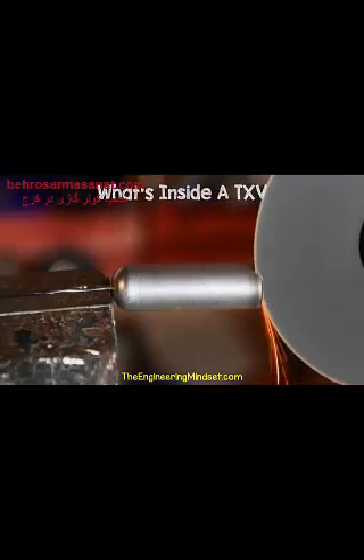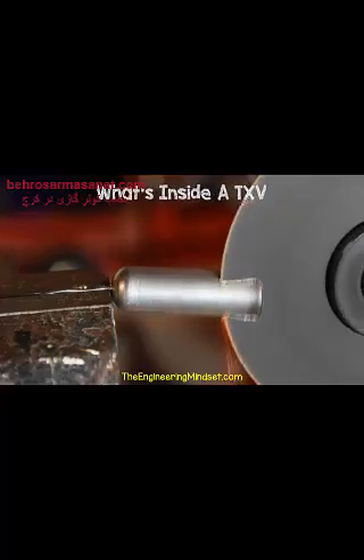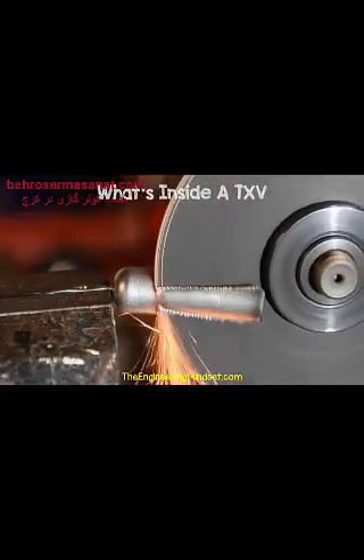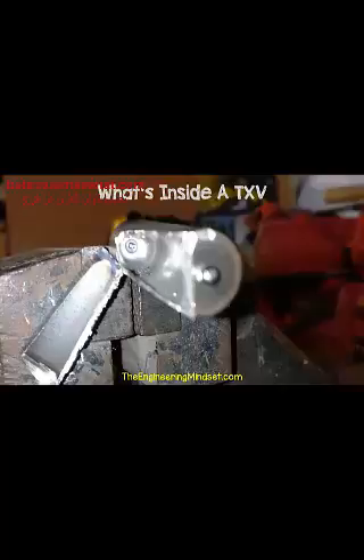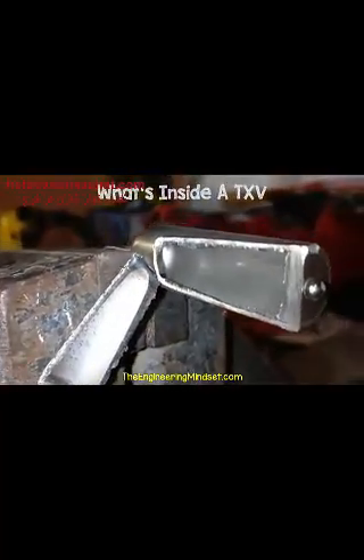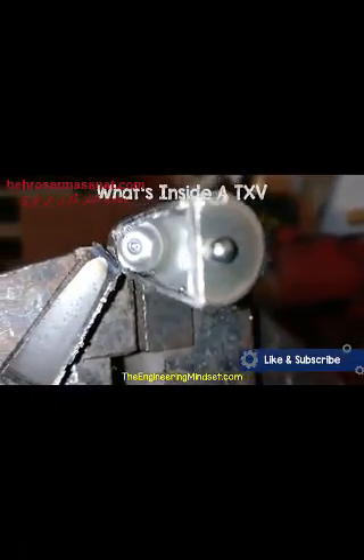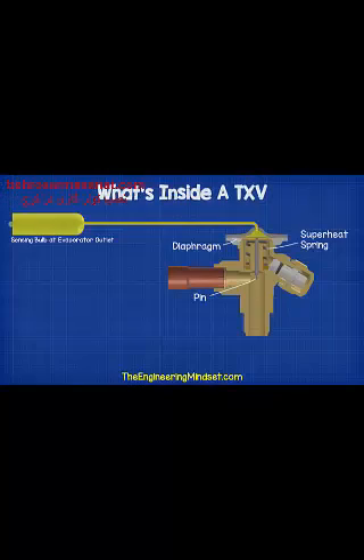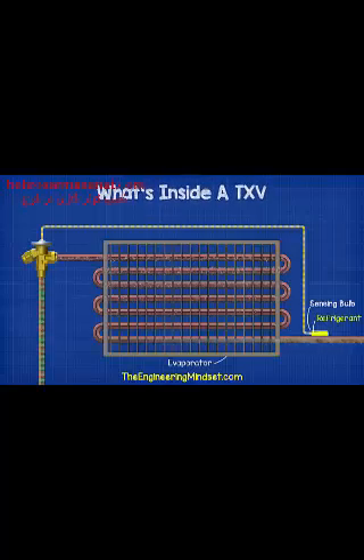I'll just cut through the sensing bulb using an angle grinder to show you the inside. As you can see, it's just an empty cylinder which is usually filled with some refrigerant. The refrigerant in the bulb and capillary are completely separated from the main refrigerant which flows in the system. This isolated refrigerant only moves between the bulb, the capillary tube and the top of the diaphragm. The sensing bulb sits at the outlet of the evaporator.